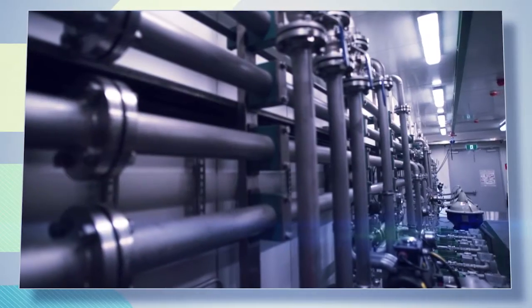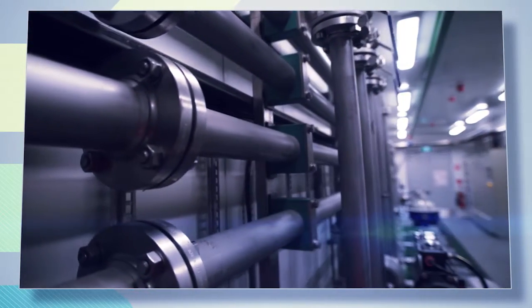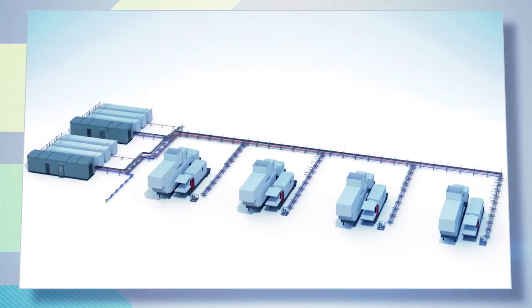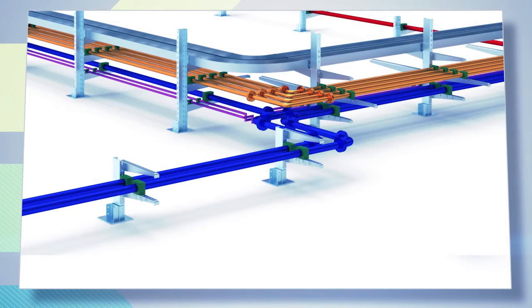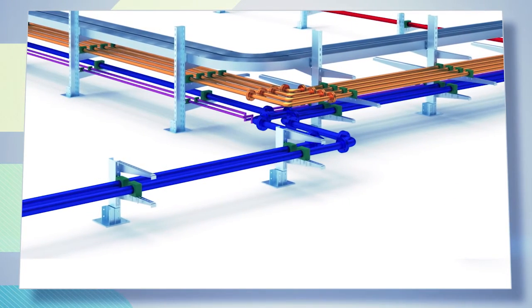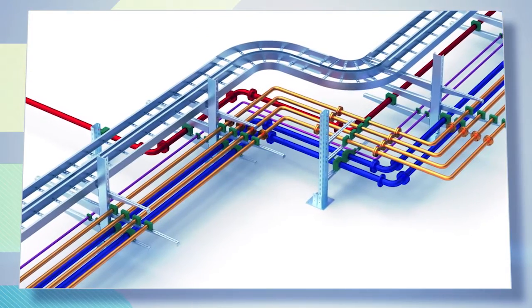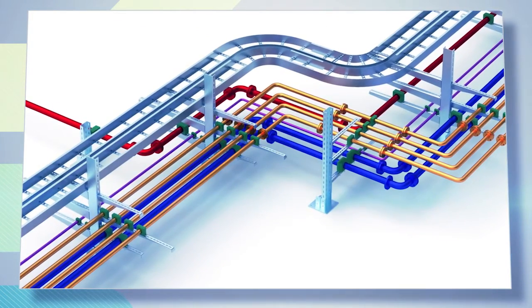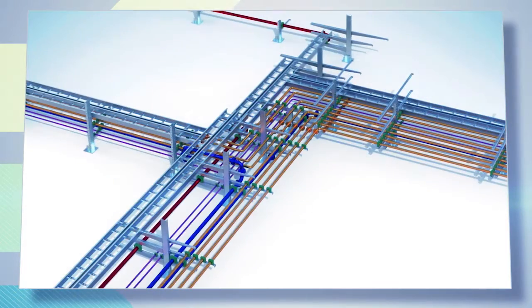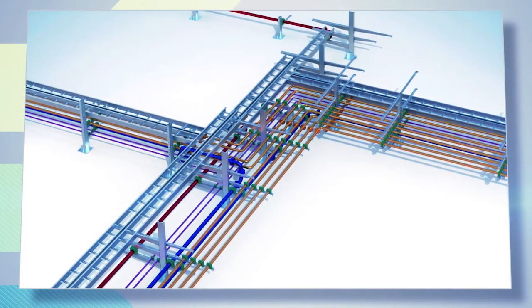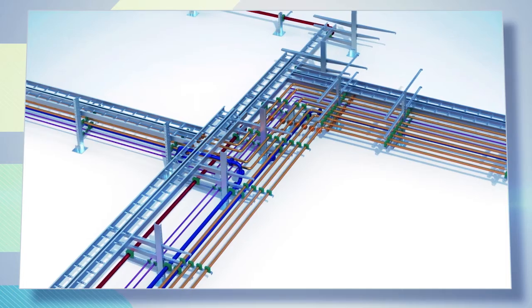Pressure piping for the fuel block and all modules is fabricated from stainless materials. RJE has extensive experience with site piping and cable design and construction. Standard piping and racking packages can be supplied for 1, 2, 3 or 4 generator sites. The system is fast to install and all spools are cleaned, flushed and capped prior to dispatch.